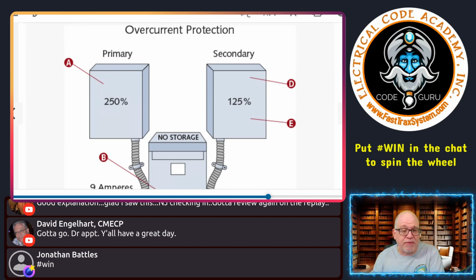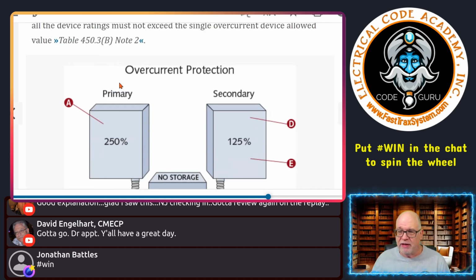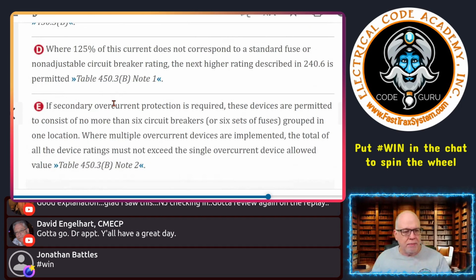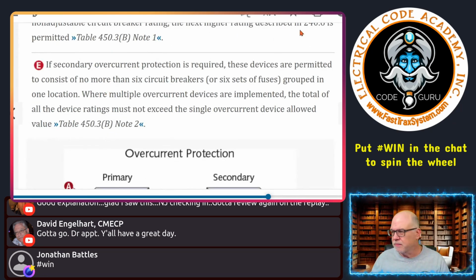Now, how does this differ from previously where you could go to 125? You can't round up here. You can't say, oh, 250 on a primary doesn't correspond, I'll go to the next standard size. No, it's not how it works here. That's how it worked before, but that's not going to work that way here. Okay, and I can show you that. But let's go to 450 real quick again.